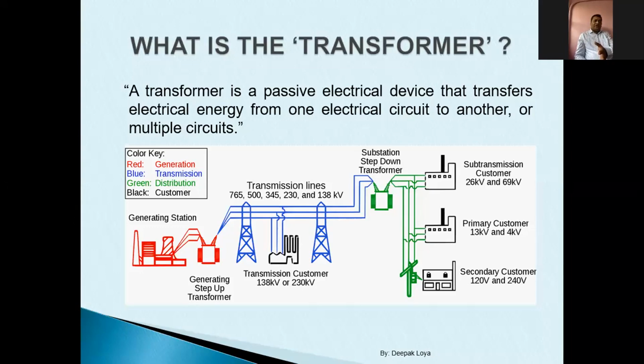Now, why do I need a transformer? I can just connect cables to one circuit and get the power. But friends, each circuit has a different potential level or voltage level. For example, if I have a diesel generator set, a DG set, in my house, the generation voltage of the DG set would be equal to my load voltage. That means single phase may have 230 volts, or if it is three phase, it may have 415 or 433 volts.